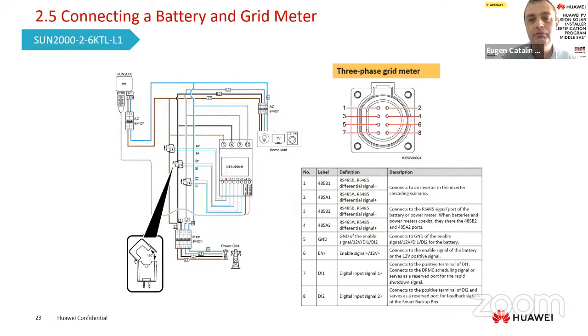Act how? It will control the power with the information received from the meter, or it will show you the correct or wrong value in Fusion Solar. This is very important to check before you power on everything: check if the meter is correctly installed and that it measures the power correctly.